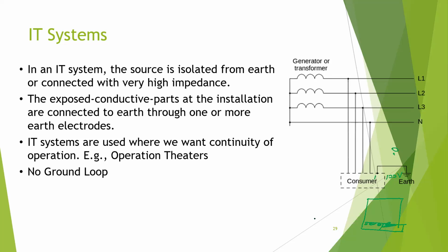IT systems are usually very specific kinds of systems, only used in operation theaters and special locations. And the main advantage is you can use this system without an issue even if there's an earth fault. That is the main advantage of the IT system. The only issue is if you have a fault from another line, it is called a double fault. If this enclosure is energized to 100 volts by one line touching the enclosure, and another line touches the enclosure, there will be a short circuit between two phases, and you cannot keep continuity of operation. That is one of the things you should consider in IT systems.